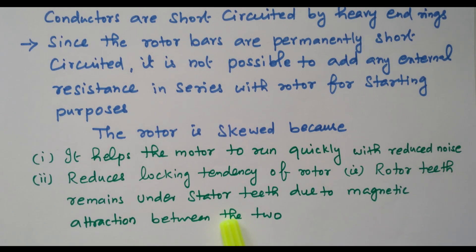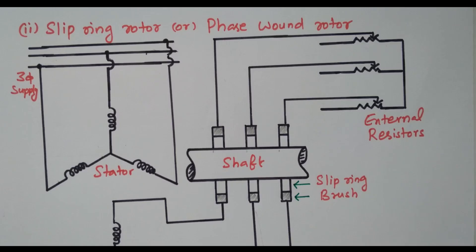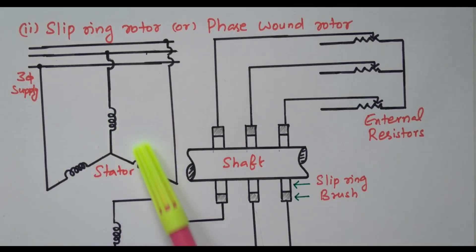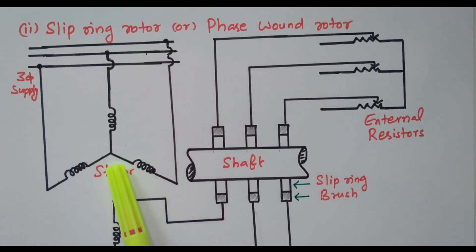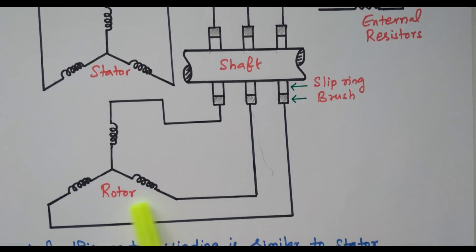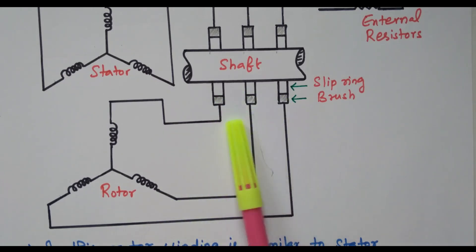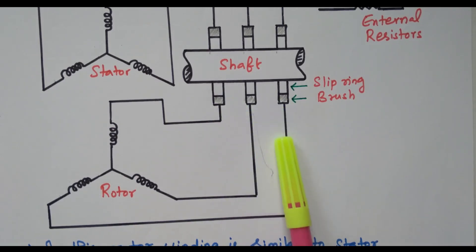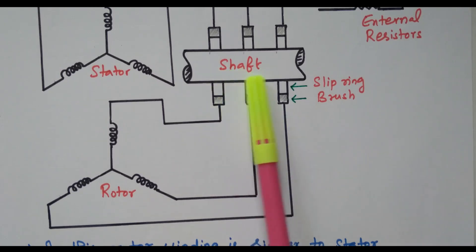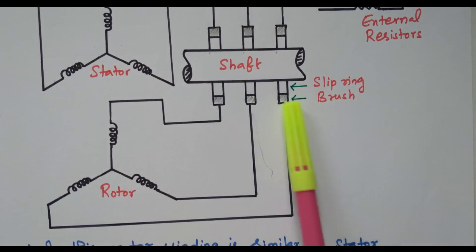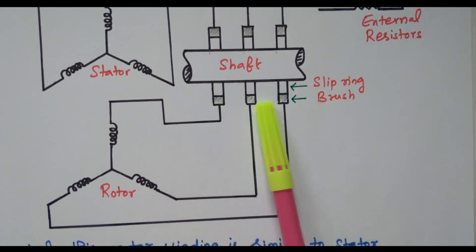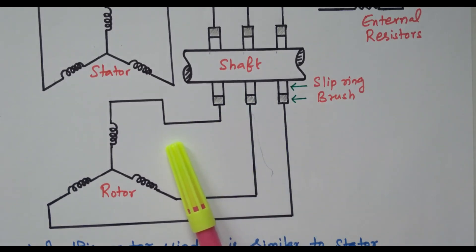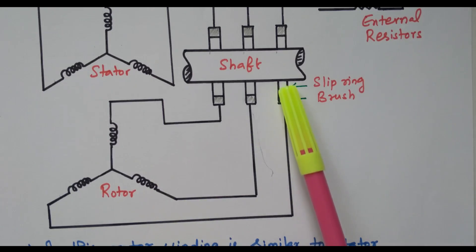Now we will go to the second type: the slip ring rotor or phase wound rotor. In this type, separate windings are available for the rotor. The stator receives three-phase supply. The rotor winding is star connected and connected to slip rings. Through the slip rings and brushes, supply is given to the rotor windings. The shaft is also visible in the diagram — the shaded portion represents the brushes and the other portion is the slip ring. Unlike the squirrel cage rotor, here the windings are placed instead of copper or aluminum bars, and supply to the winding is given through the slip ring and brushes.